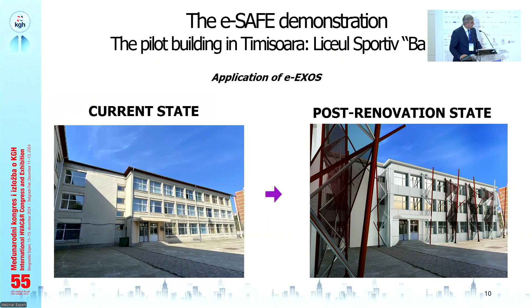Related to the energy performance conception, we have a thermal system with minimum energy demand. Each is supposed to have high-performance air-to-water electric heat pumps, insulated water tanks to store thermal energy, full DC inverter technology, refrigerants with low GWP preferred, fan coils fed at low-medium temperature less than 45 degrees Celsius, a small storage tank for domestic hot water of 140 liters, and floor heating if necessary.